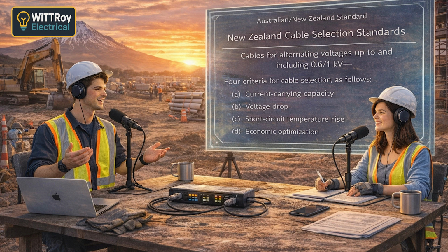Good question. Let me ask you this. What do those tables assume? Maybe normal conditions? Yes, ideal conditions. So not too hot, not grouped, not in insulation. Exactly. But real life is never like that. Correct. So that means the table values are kind of optimistic. That's a good way to think about it. So then we reduce them. Yes, we apply derating factors.